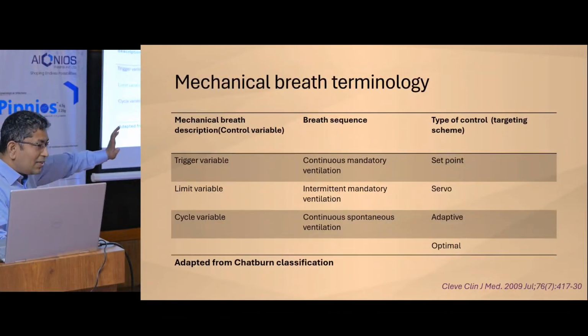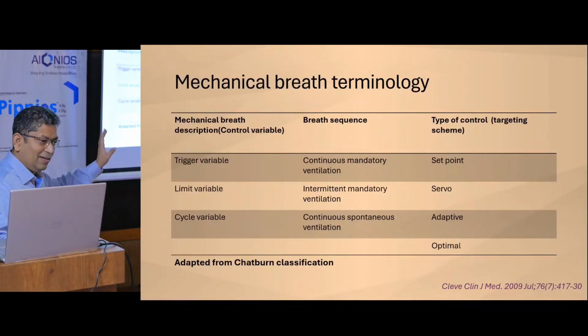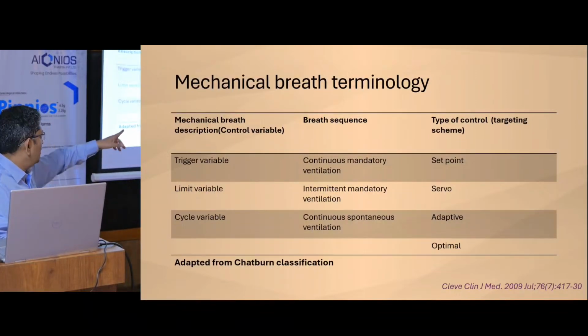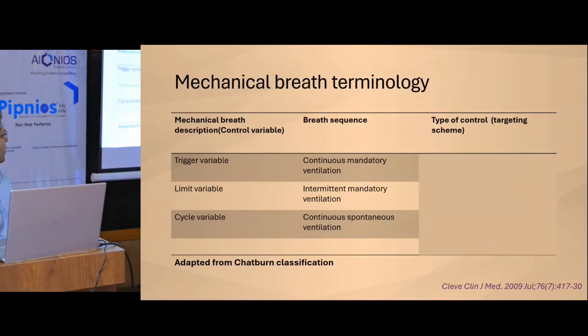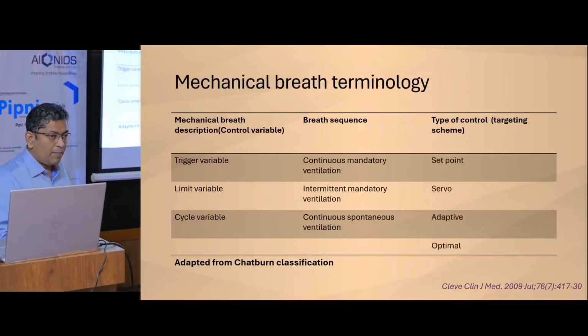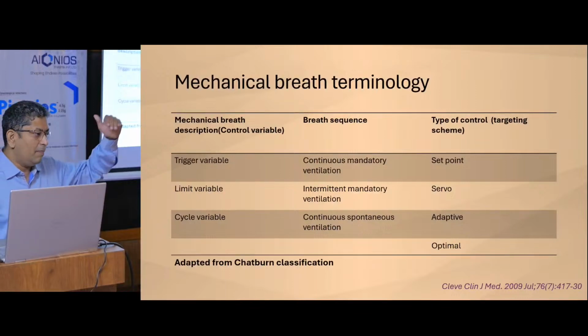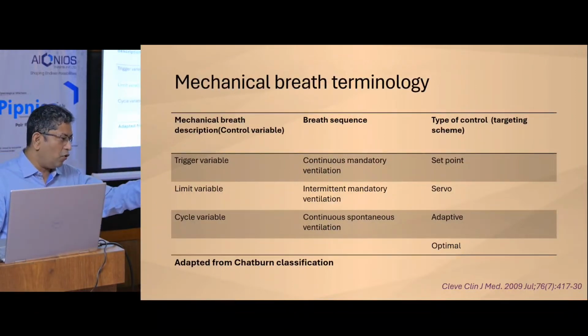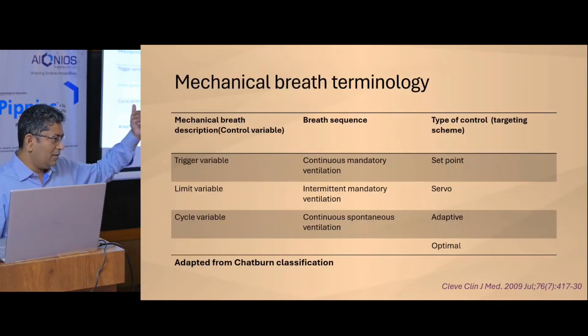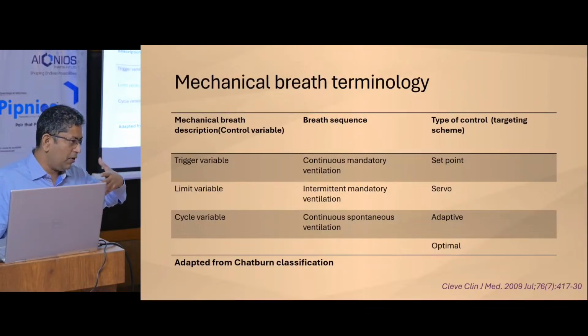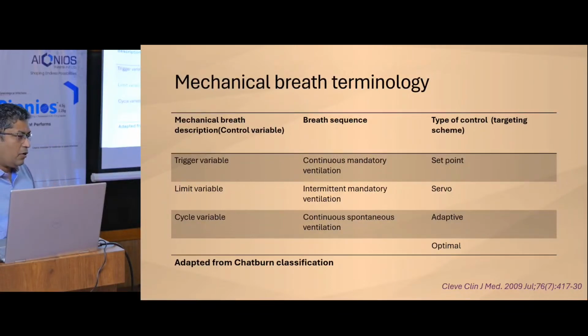Now, that's not the only thing that we have there. So now you understand why people call it mandatory ventilation, spontaneous ventilation. Yeah, SIMV has both, right? And for type of control, generally in most of the classical ventilators it is the set point, like pressure is set, or the volume is set, or the flow is set. So you set a point for how the ventilator will give the air. Okay, so the targeting mechanism is by the set point. But there are newer modes which have other things like servo, adaptive, and optimal kind of control. We'll come to that.